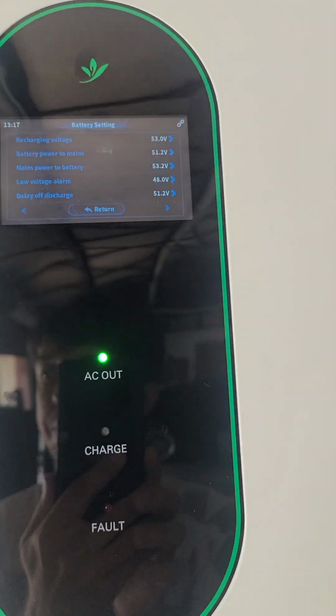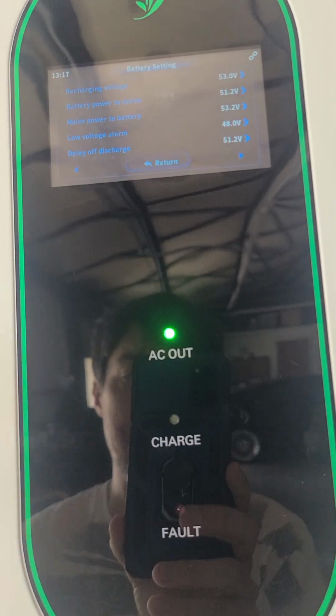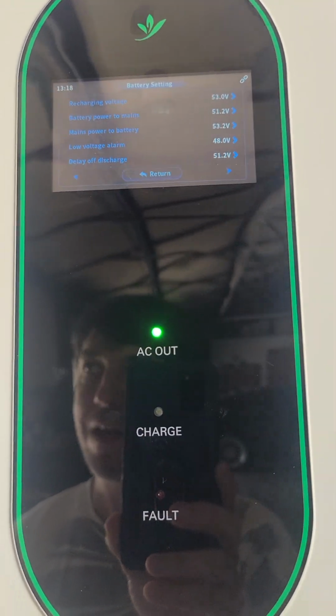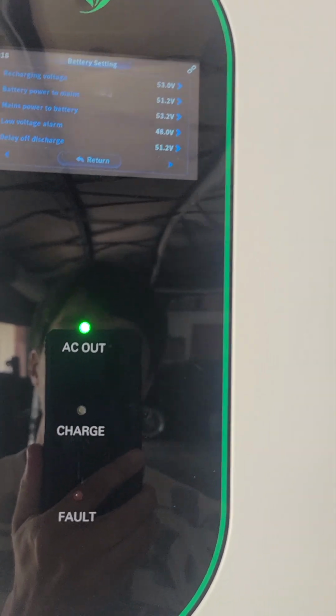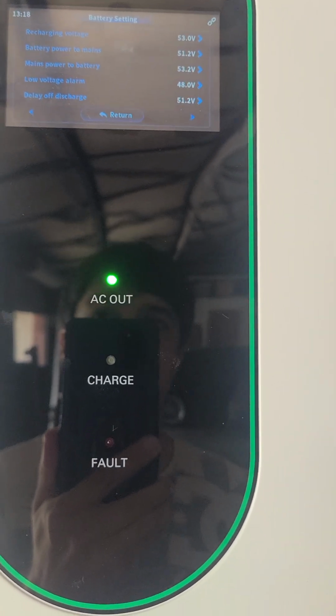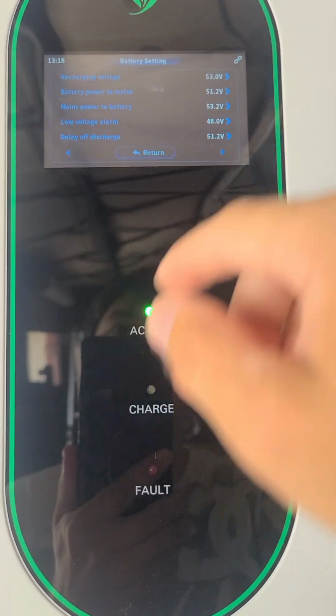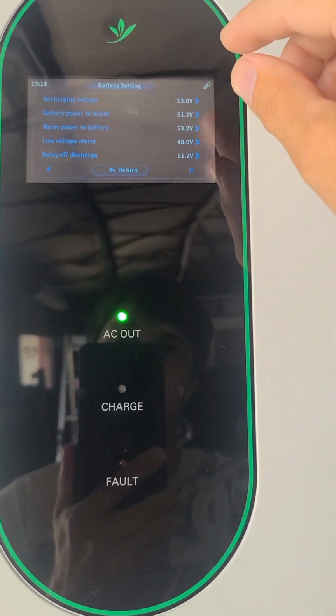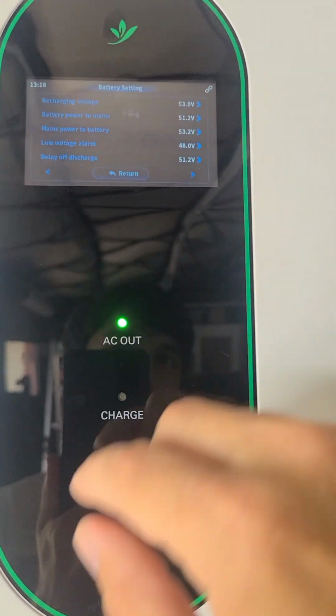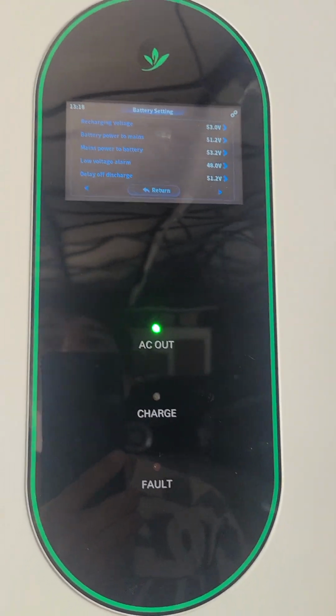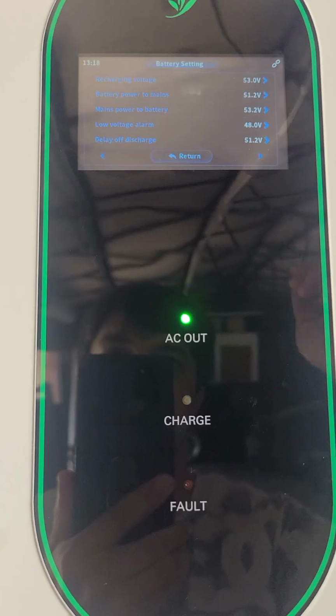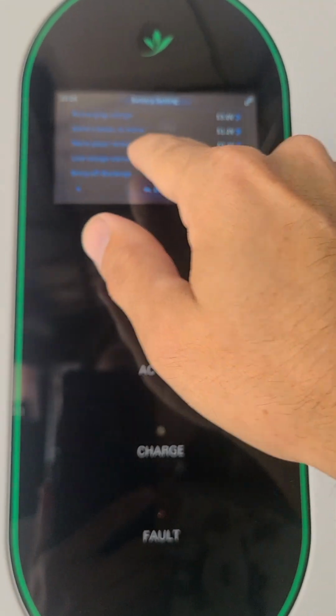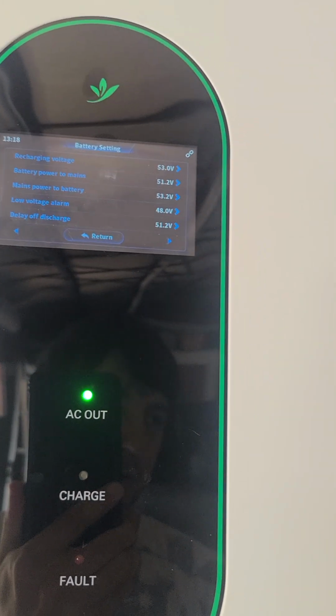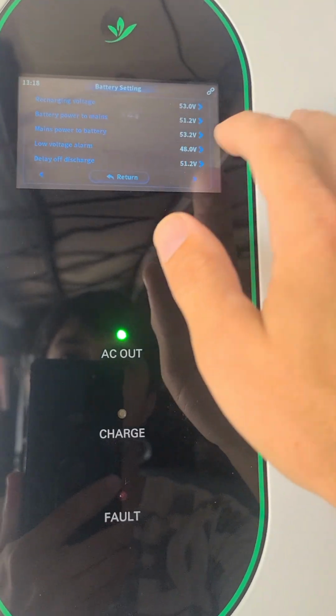Now these battery power to mains and mains to battery power settings are only for battery mode, and battery mode is pass-through mode, which is what I described in the wiring setup that I want to eventually set this up to, and I will. I gotta buy some things, and I gotta have an electrician come out here to do the interlock. It's gonna happen. It's just gonna take probably another couple weeks to a month. Anyways, so those two settings are for that. So 51.2 volts is 20% charge on this battery pack, and 53.2 volts is 80% charge. So what I'm saying here is when we're in battery mode, when we get below 20% charge, stop using the batteries, use the mains. When we're above 80% charge, stop using the mains at all. Just use straight battery.